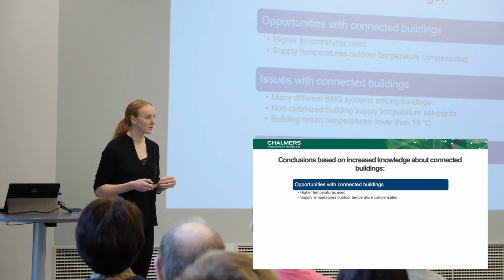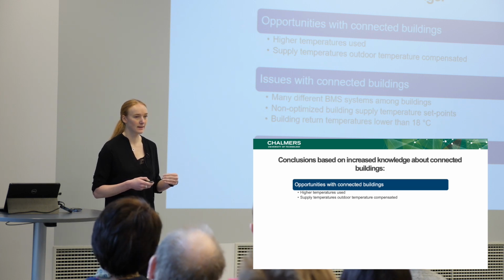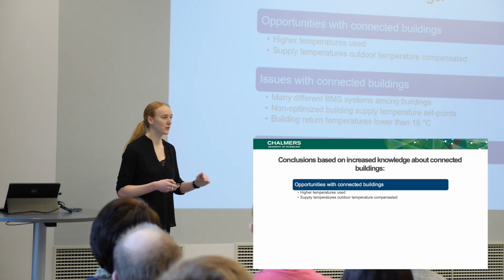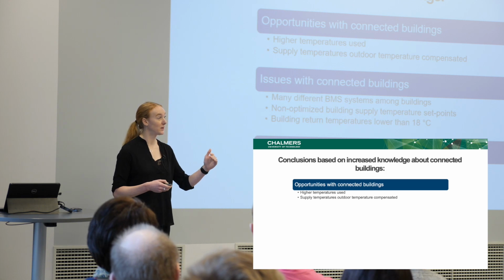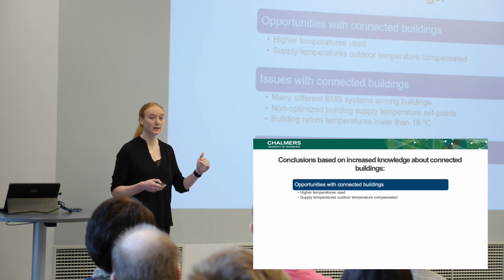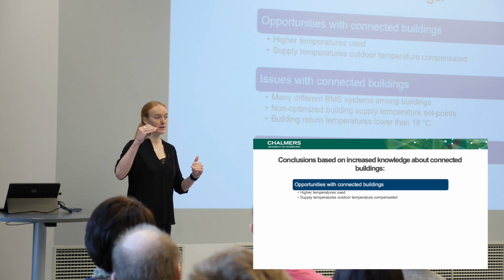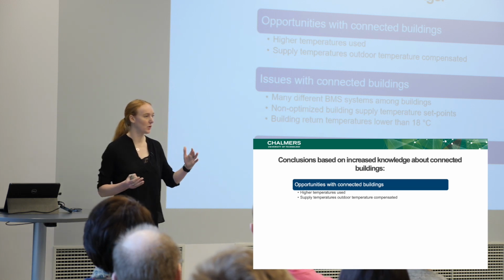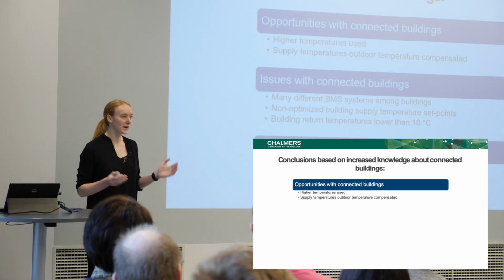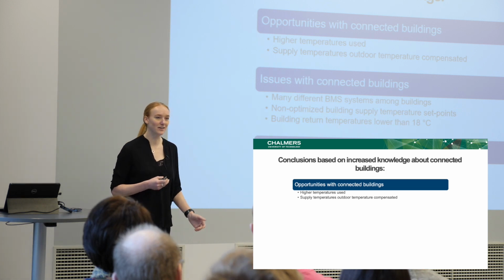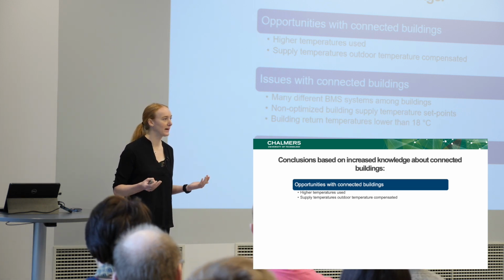So if the district cooling side can't keep the 6 degrees for a few hours, it might jump up to even 8 if they have troubles with production. Then the supply temperature has to follow on the building side. Otherwise, all the control valves will just open and let maximum flow through, and they're going to have an even harder time supplying the cooling.